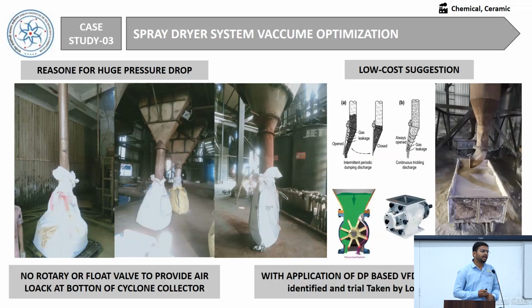This ID fan runs 24 hours in the spray dryer unit, and it is the major power consumer, with almost 40% of the power consumption going into this ID fan alone. So we can have significant savings through implementation of a VFD in this system. We demonstrated this vacuum-based system with VFD, and we can achieve up to 40% energy reduction in the spray dryer system.